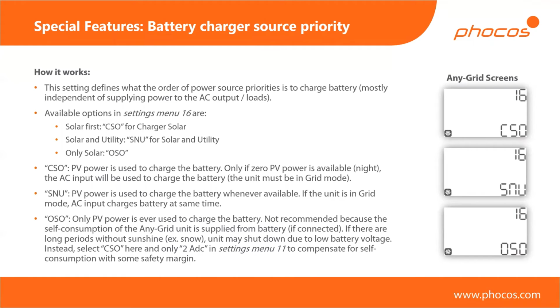And you can change the setting on how much current you want to take from utility for charging. So you can use a small setting for that. You can say, okay, I only want to charge from utility with 10 amps. And when the sun is shining, you can charge with up to 80 amps, for example. Then we have the solar and utility, where we're using both simultaneously to charge the battery. And then finally, we have the only solar setting, where we're absolutely forbidding any charging from happening from the AC input.